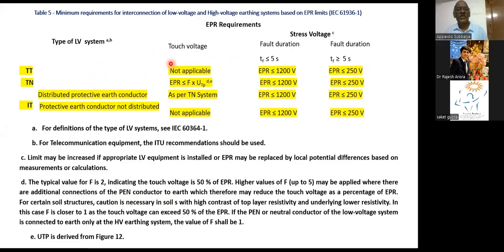Temporary overvoltage is something different from your lightning surges. Lightning surges persist for, say, a microsecond. But the temporary overvoltage, due to a fault in the supplier's distribution or the transformer, a line to earth fault, can be controlled by the supplier's circuit breaker at the substation, depending upon the fault level. Consumers are not aware of these two things. That's why the standards prescribe that it should be made accountable.